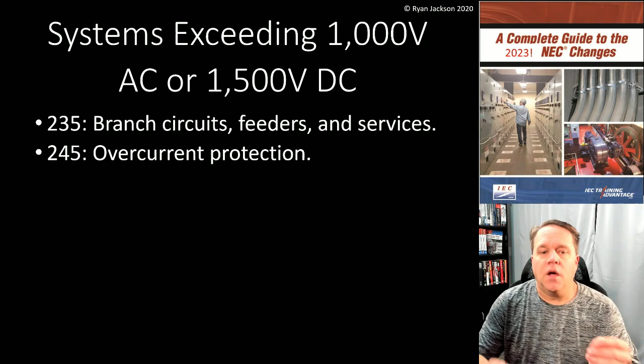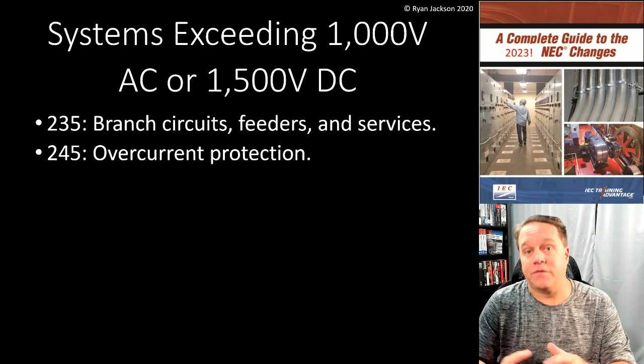Article 245 is actually a lot bigger than you might think. If you went to Part 10, or maybe Part 9, of Article 240 in previous versions, it was seriously only like 2 paragraphs for 1,000 volts. When you get into Article 245 in the 2023 NEC, you'll find it's a lot bigger than just 2 paragraphs, because they relocated some of the stuff out of what used to be Article 490 and moved it over to Article 245. This effort made everyone aware that maybe we needed some new requirements and provisions for these systems. So Article 245 is overcurrent protection.